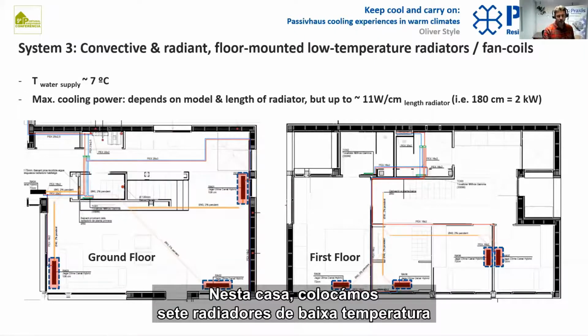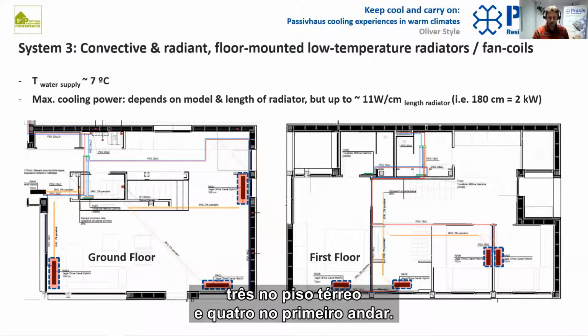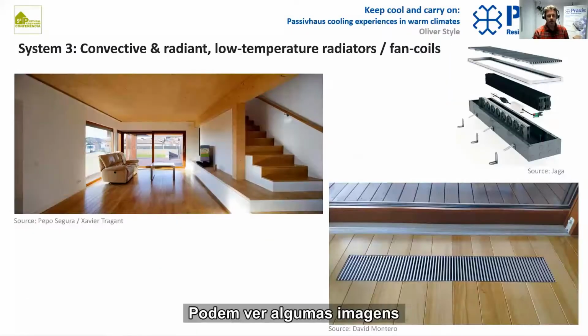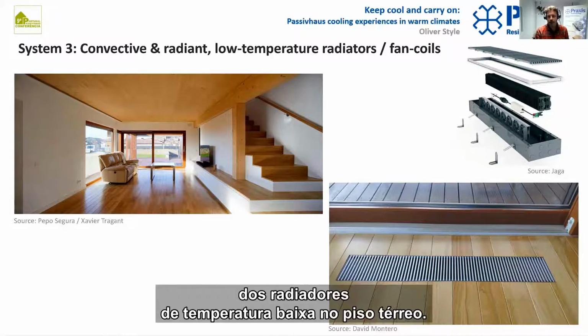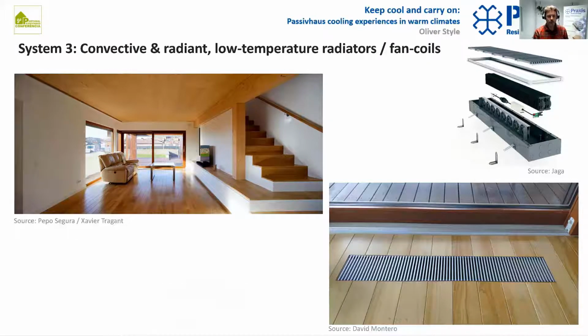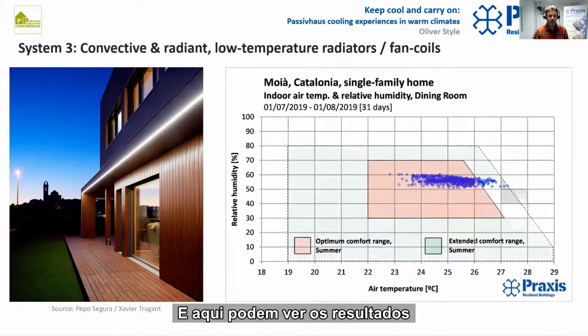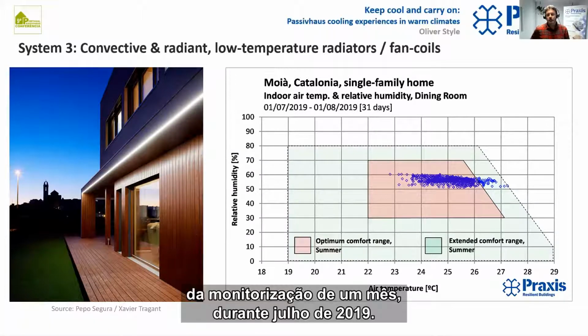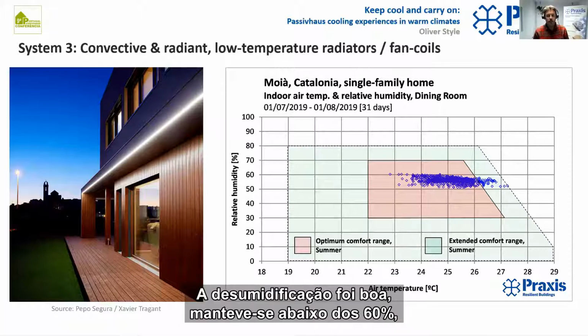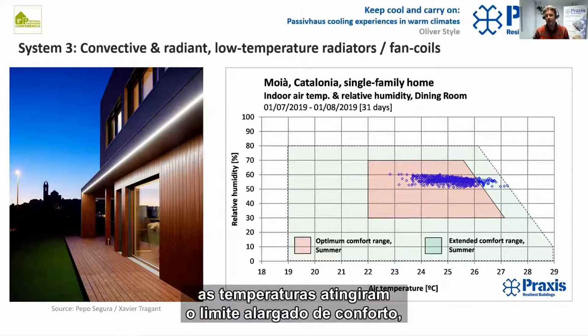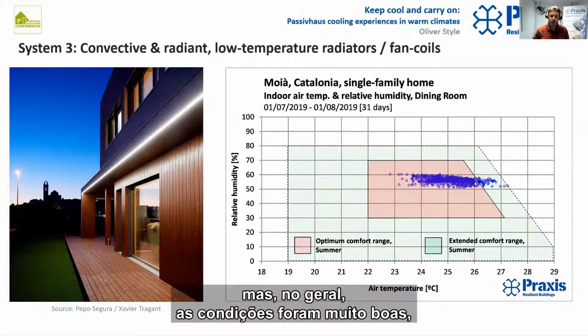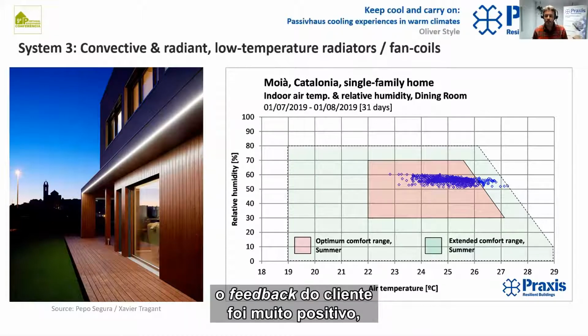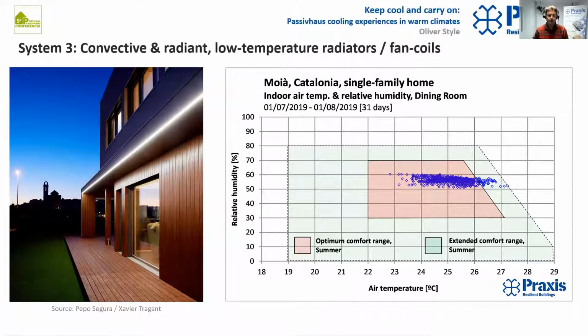So in this home, we located 7 different low temperature radiators, 3 on the ground floor, 4 on the first floor. Here you can see some images of the low temp radiators on the ground floor. And here you can see the monitored results for 1 month during the summer, July 2019. So basically good dehumidification, that's kept down below 60%. Some hours in which temperatures are into the extended comfort range, but basically pretty good conditions, very positive feedback from the client, and a good solution.